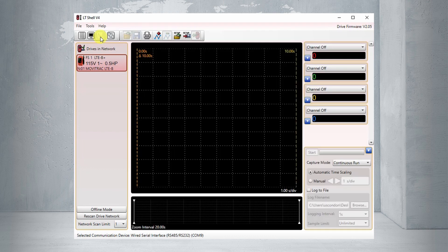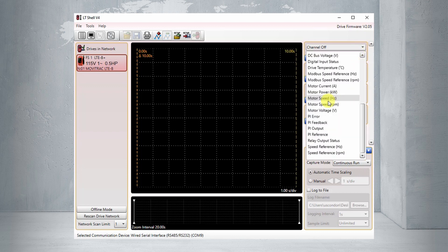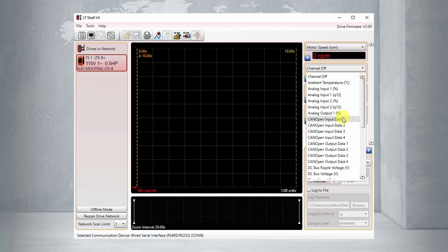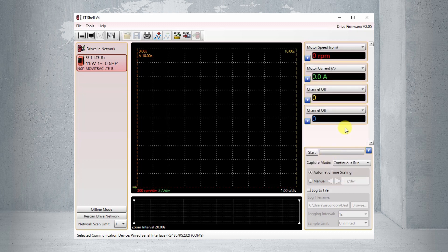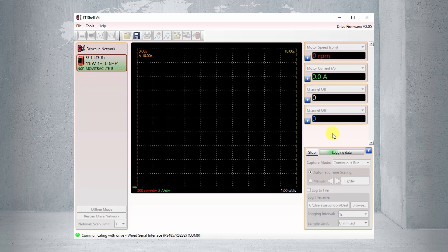In the scope, we need to make sure we're in Continuous Run mode as our Capture mode, then pick our channels. I'll use just two channels: channel 1 to monitor the motor's speed in RPM, and channel 2 to monitor motor current in amperes. I'll turn Digital Input 3 on so we don't trip a fault, then turn Digital Input 2 on to select Preset Speed 1, and finally turn Digital Input 1 on to ramp up the drive to 1500 RPM. Once it's up to speed, I'll let it run for a few seconds and then bring it back down again.